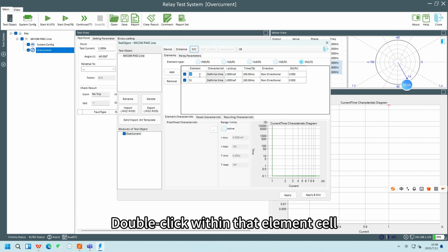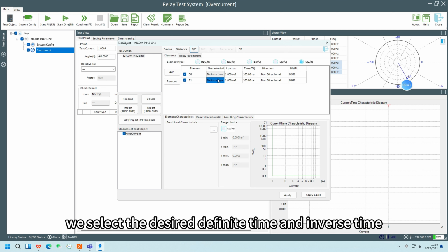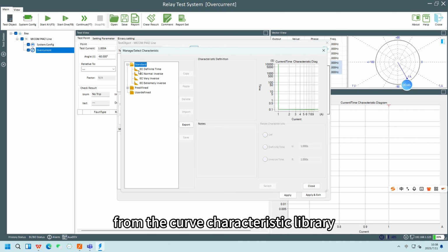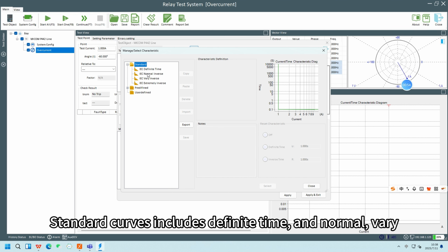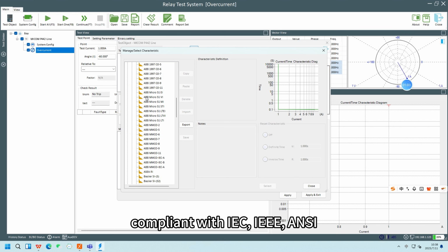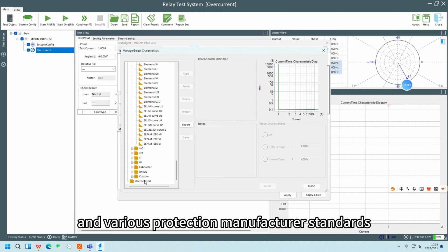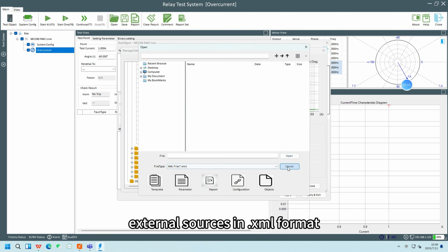Let's move on to element settings. Double-click within the element cell to assign a descriptive name to our element. Choose the time characteristic. Here in the element characteristic we select the desired definite time and inverse time from the curve characteristic library. This library offers standard curves, predefined curves, and user-defined curves. Standard curves include definite time and normal, very, and extremely inverse time options. Predefined curves feature a comprehensive collection of inverse time curves compliant with IEC, IEEE, ANSI, and various protection manufacturer standards. User-defined is where we can import curve data from external sources in .xml format.